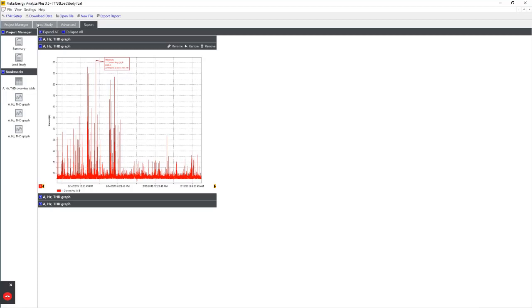And you can also do some characterization of event information, but not in detail. You can also capture total harmonic distortion for voltage and current to quantify if you really do have a significant amount of harmonics in a system, which could cause effects like overheating in motors and transformers.